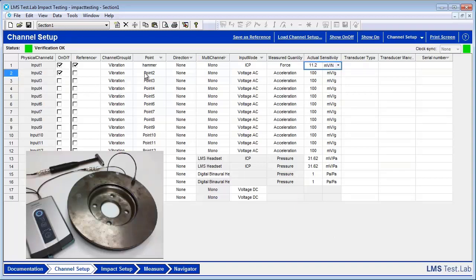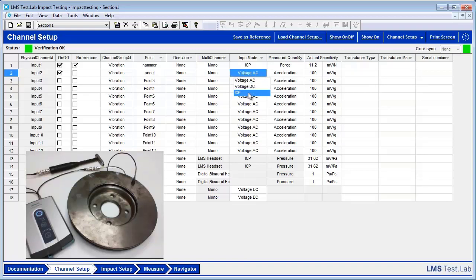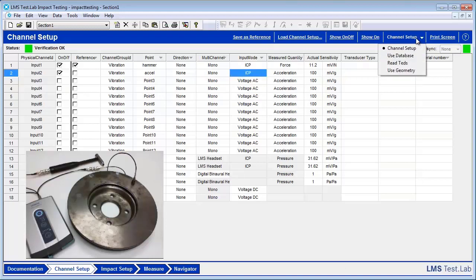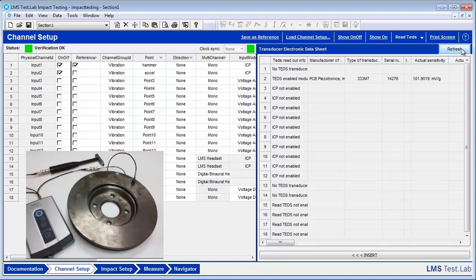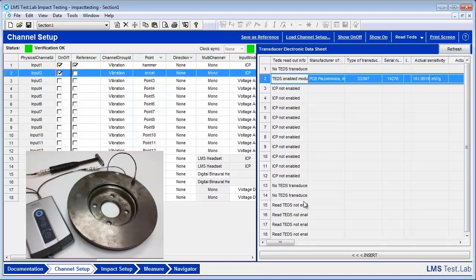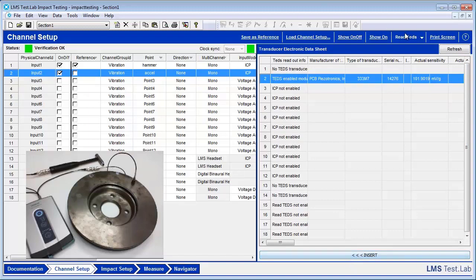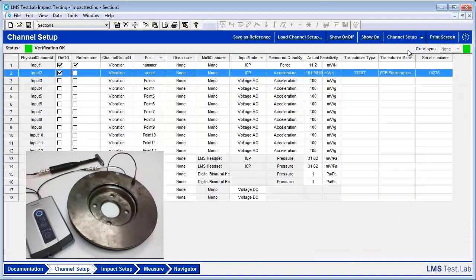And we can go through these steps for the accelerometer. Change this to ICP. Then actually, with this accelerometer, we are able to go to this top right here, Channel Setup. Select Read TEDS. TEDS is our transducer electronic data sheet. So what this does is when we hit Refresh, the information for the accelerometer comes up in Test Lab. You can select this. Insert. Go back to our Channel Setup page. And as you can see, Test Lab adds in the actual sensitivity for the accelerometer, tells us the transducer type, and even gives us the serial number.